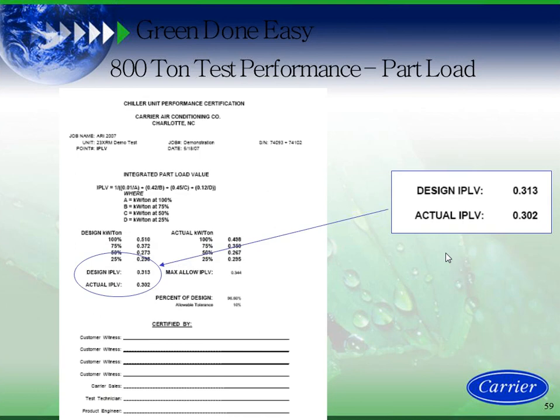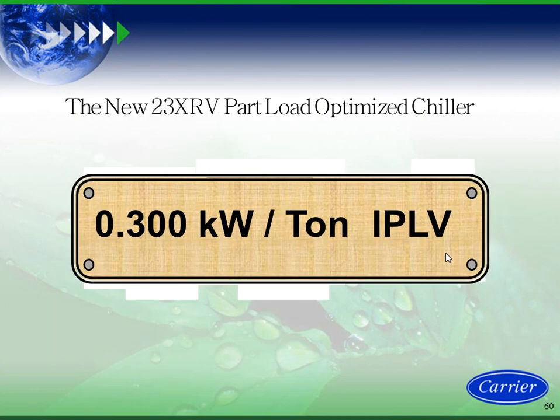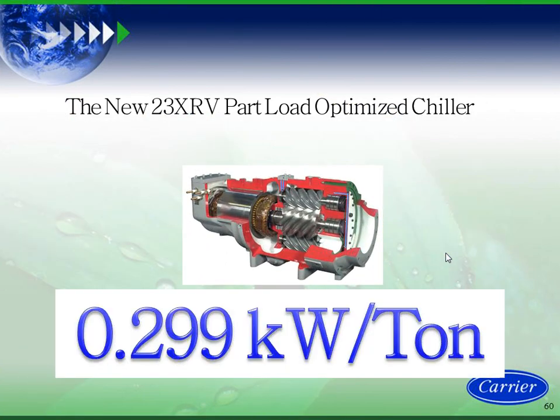Okay. Now you say, how can we actually do better than this, right? Well, we came out with something called a 23XRV part load optimized chiller. I went over this in the last presentation, but what we did is Carrier basically optimized around the part load, the place where the machine operates the majority of the time. Not the 100% load point, but the 75 and below points in the chiller operation. And we are able to break the 0.30 kW per ton barrier. No chiller in the industry has ever done that, and we achieved a 0.299 IPLV on that chiller.